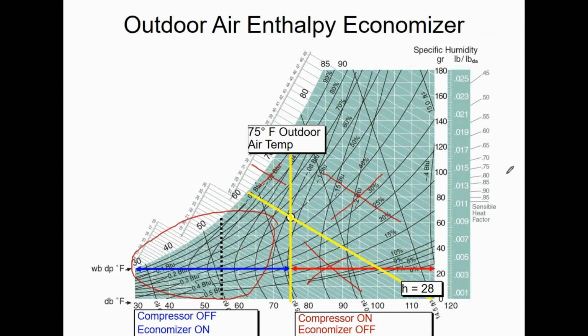So the enthalpy control, while it is one more control widget to buy and install, it does help us significantly on making sure we don't have those relatively cool 68, 70-degree days that have high humidity, right? That's what helps us avoid that. In exchange for being able to eliminate that section, that triangle of death, I, on the flip side, have to accept all this air here between 70 and 75 that I would not have accepted on a dry bulb day. All right, so those are my choices. 70-degree dry bulb set point or 75-degree dry bulb set point and an enthalpy sensor set at 28 BTUs per pound.